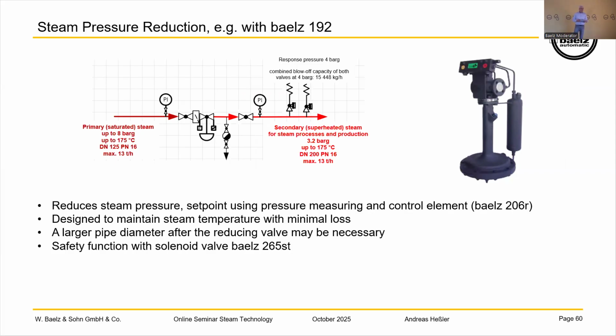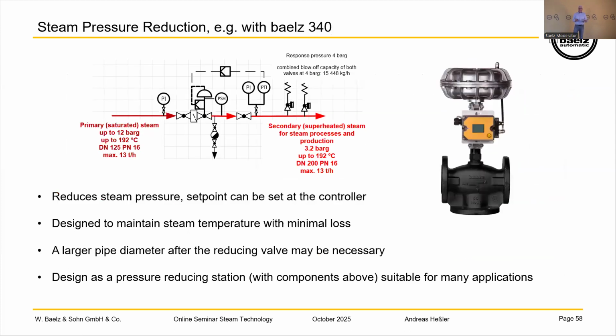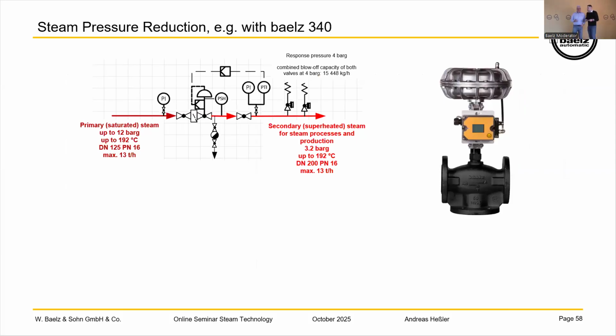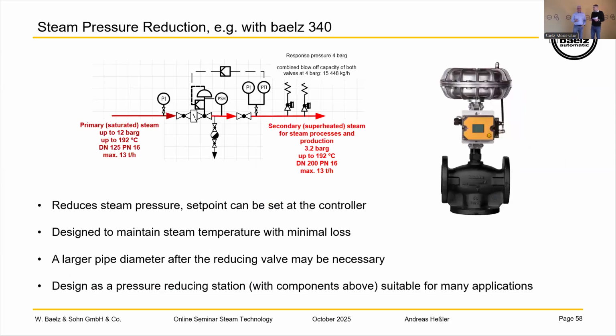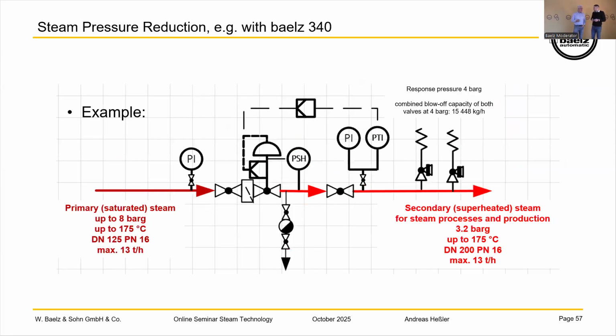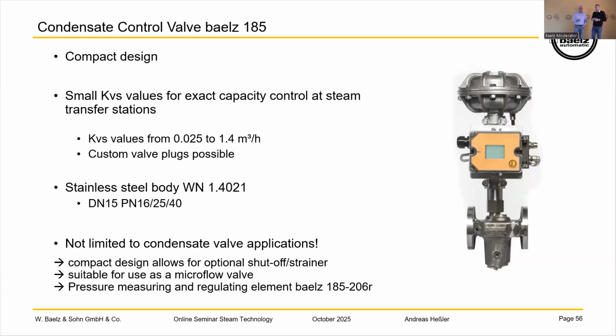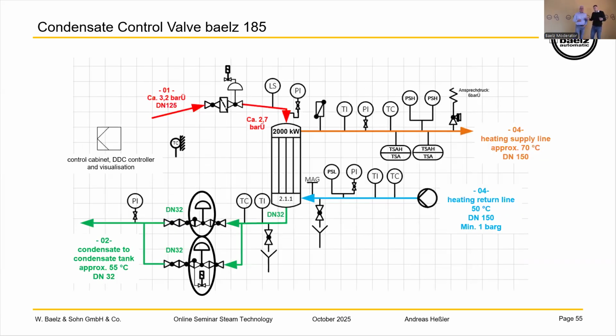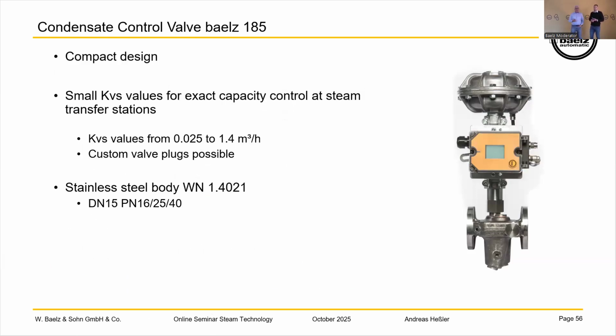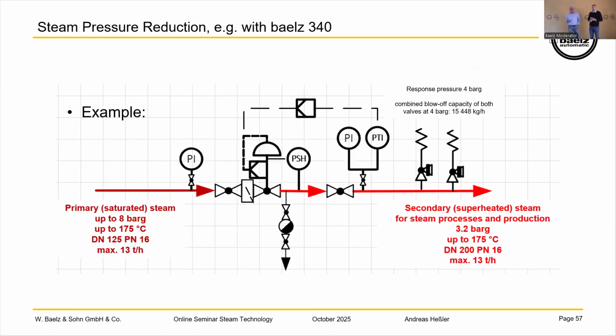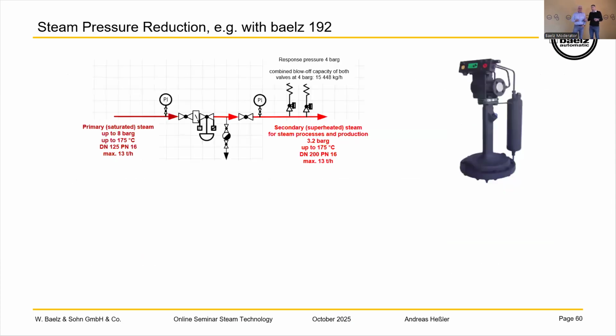How to avoid water hammering in the system? In what system? I think we would take this question and give some time to get a little more into detail. Steam hammering: one thing that comes to mind is to avoid water and steam, meaning condensate and steam, coming together. You can use steam traps, for example, as we already said about the 118. Then we have no water coming into the steam. It depends on your system what type of steam hammering you're talking about.